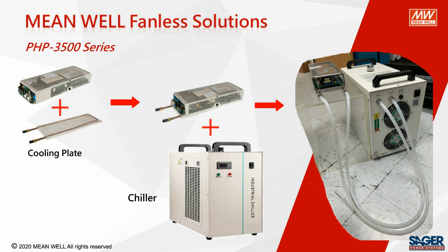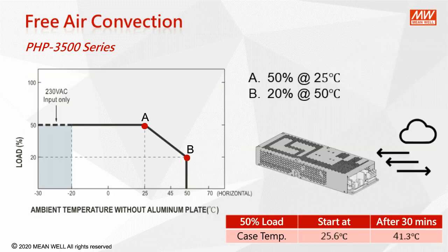On the right side is what you'd expect in a water-cooled setup. Since the PHP 3500 series supports different cooling methods, let's look at the PHP 3500 as a case study for comparing the effectiveness of different cooling methods. Shown on the left side is the output power versus temperature curve for operating under free air convection, meaning no external cooling and just the power supply by itself.